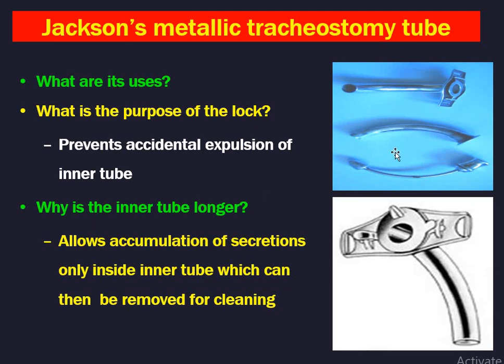Why is the inner tube longer? The inner tube is slightly longer than the outer tube so that accumulation of secretions occurs only inside the inner tube. This can then be removed for cleaning — the inner tube can be taken out periodically and cleaned. The outer tube is usually not taken out; it is changed after 7 to 10 days.